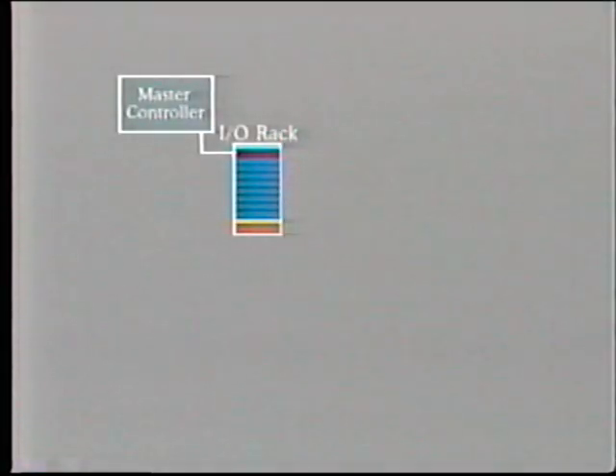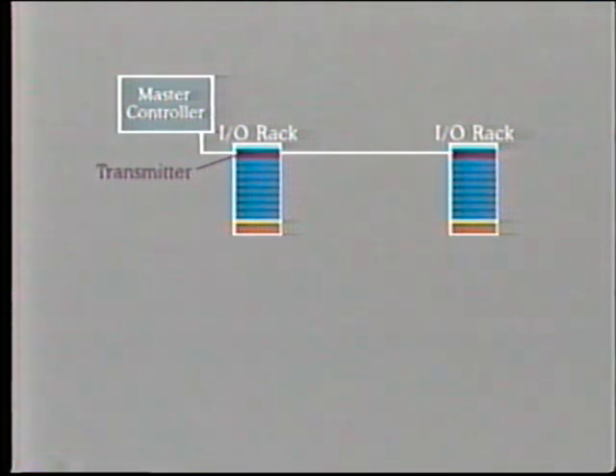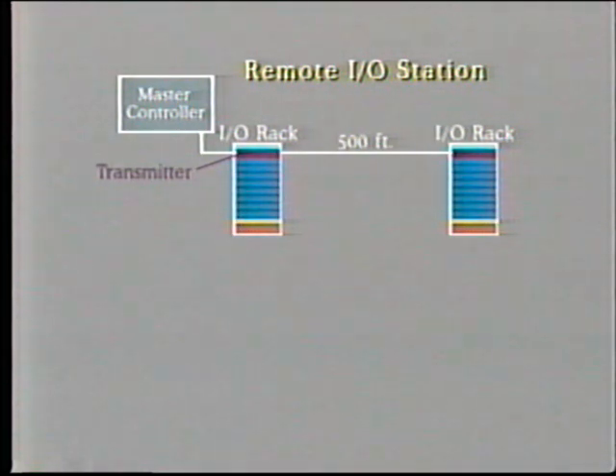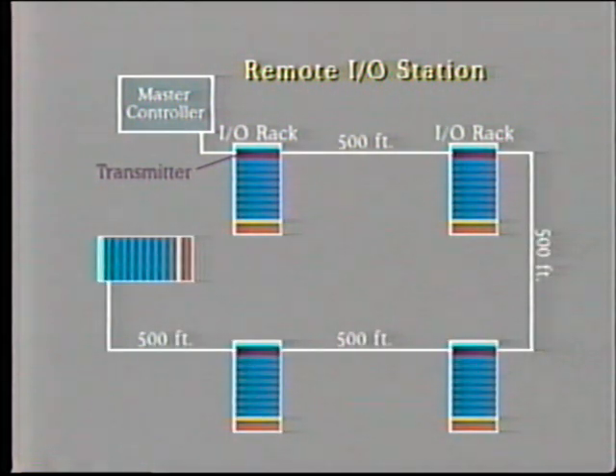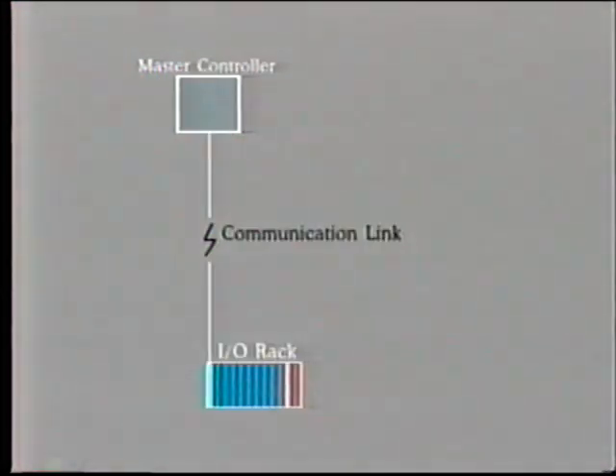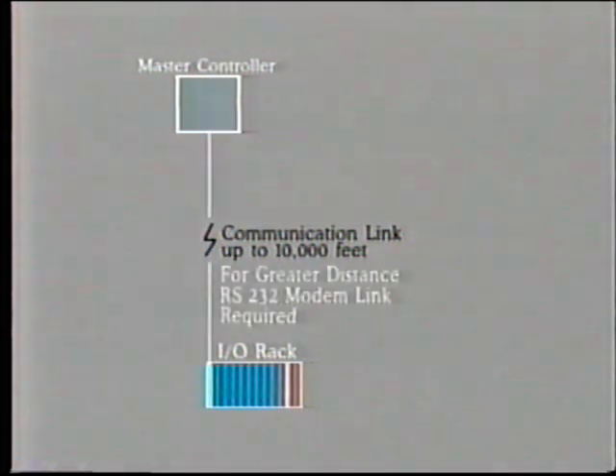If a greater distance is required, then it is necessary to add a transmitter in order to boost the signal to the next rack. This may be up to 500 feet in distance and is known as a remote I/O station. An additional 3 stations may be added in this manner, so giving a maximum distance of 2,000 feet. If a longer distance yet is required between the master controller and the remote station, then a serial communication link must be installed between them. This may consist of a twisted pair cable, which would allow a distance of up to, say, 10,000 feet. For greater distance than this, an RS-232 modem link would be required.